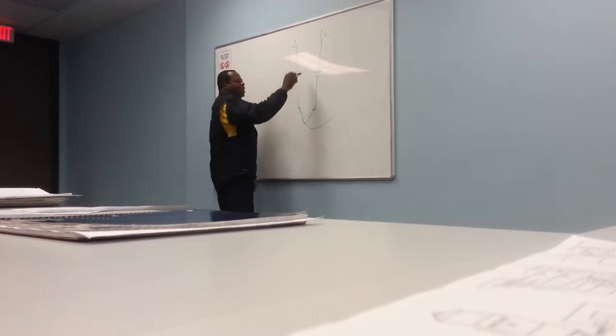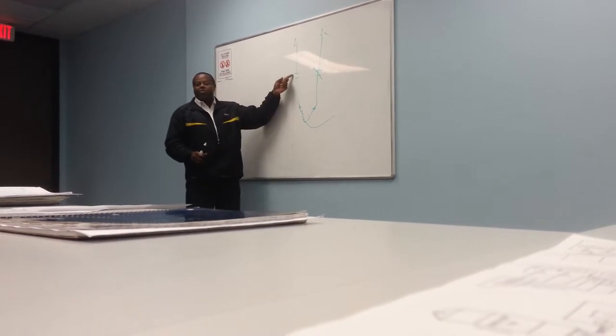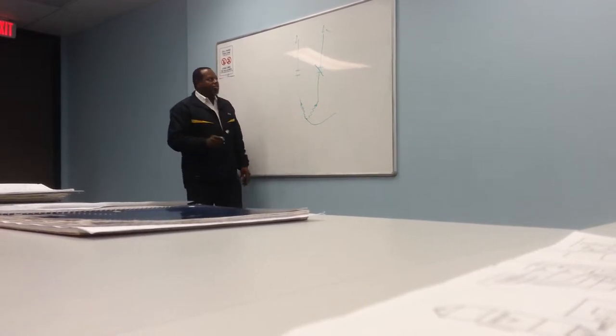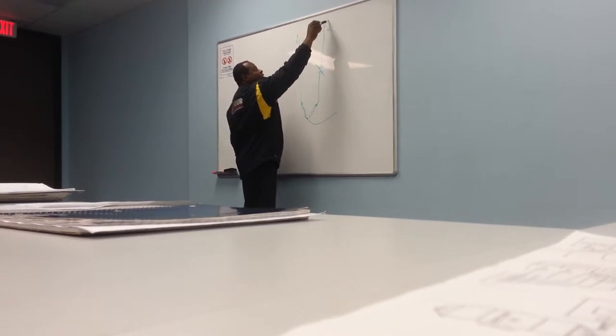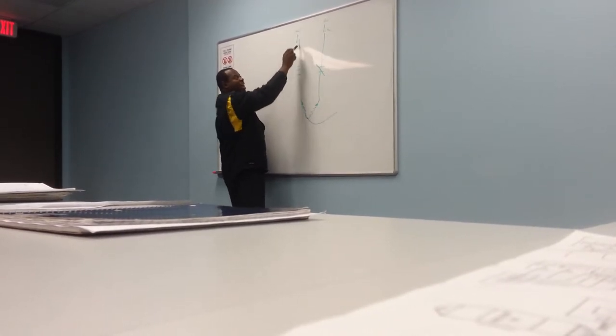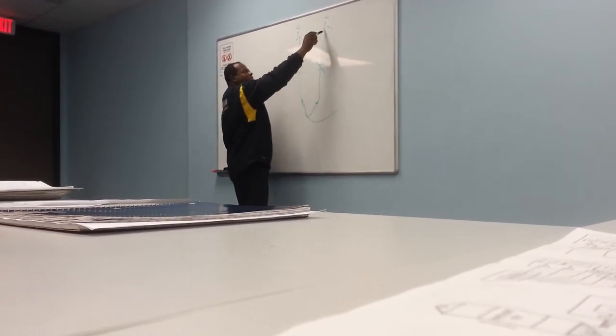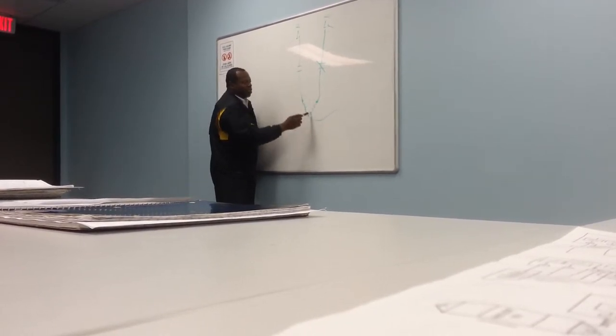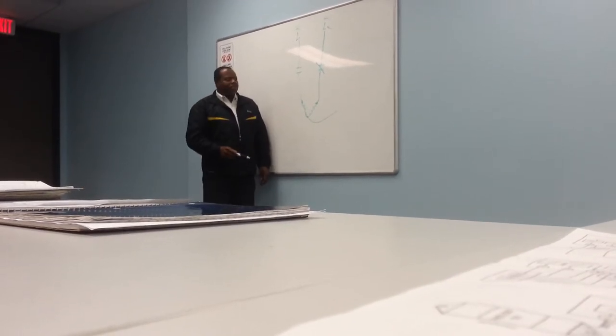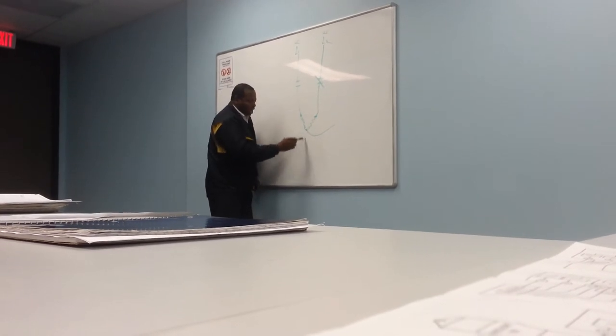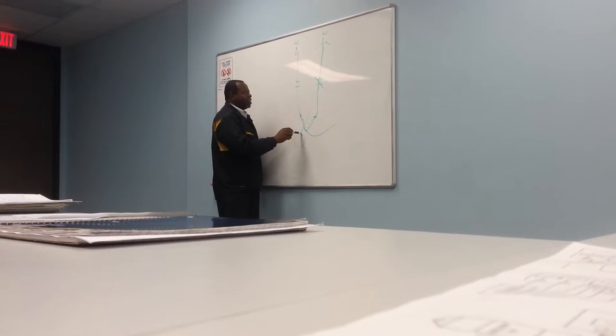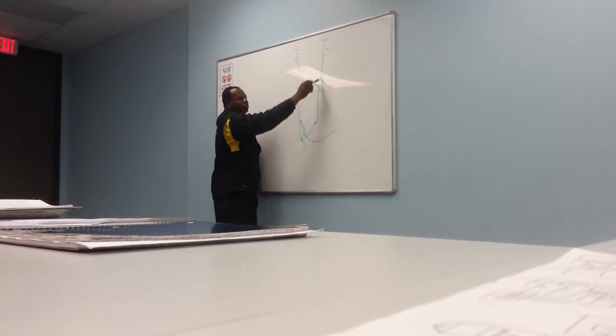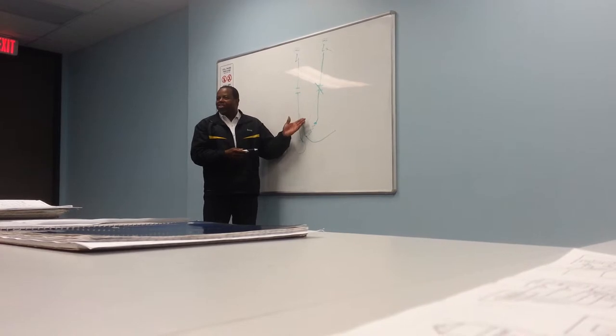So, if this one closed and this one is open, that's the same thing as when you say it's on this side, so it's not letting power through. Correct? So now look at this. Remember, this is 120, right? And it's 120 here, right? We're not getting this one, correct? So look at this. Are you getting this 120? And it's going through the compressor, coming out, coming on this side. Ain't this one circuit? Yes, it is. So when I get my voltmeter and I go from here on this side of the contactor and on this side of the contactor, what should I get? 120. Zero. Zero, because it's closed. Because I'm still on the same circuit. Understand?